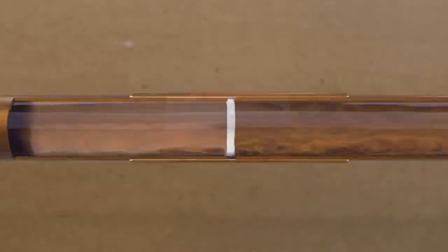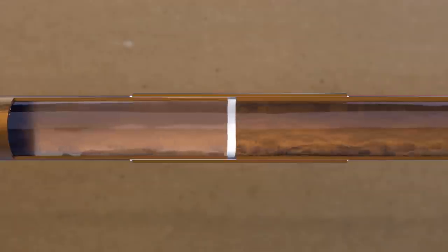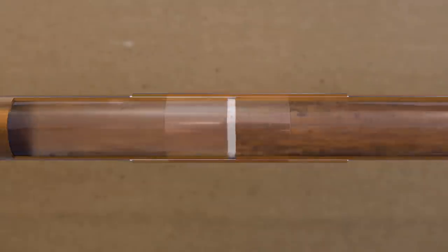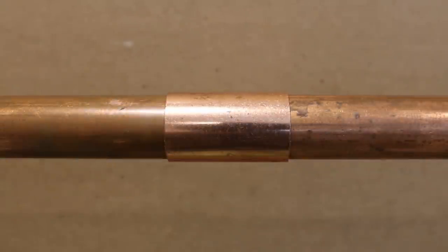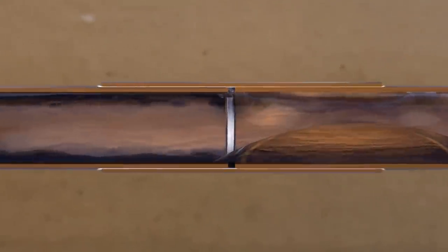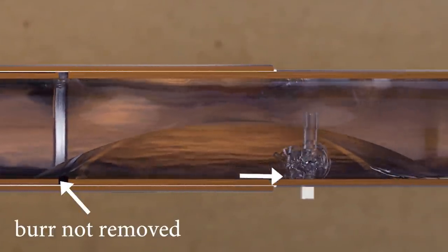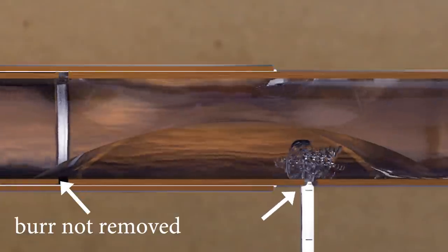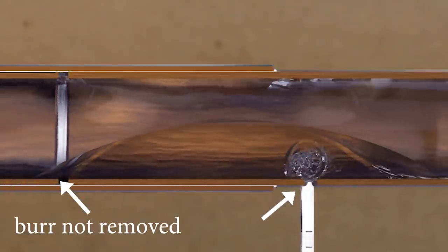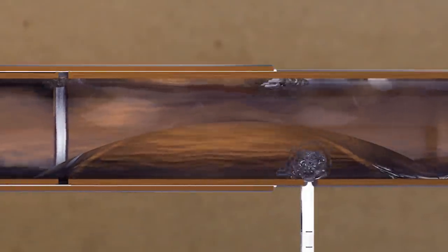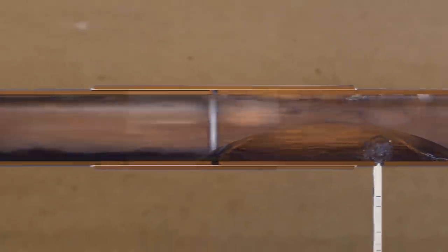If you have a straight pipe with water flowing through it like this, the water will flow straight without any restrictions, which is totally normal and exactly what you want. But by leaving the burr on, it creates a jump, or a hydraulic jump, which creates a small, constant whirlwind or vortex, which slowly erodes the pipe due to the velocity and causes a small pinhole downstream about one inch away from the fitting. This phenomenon is called erosion corrosion.